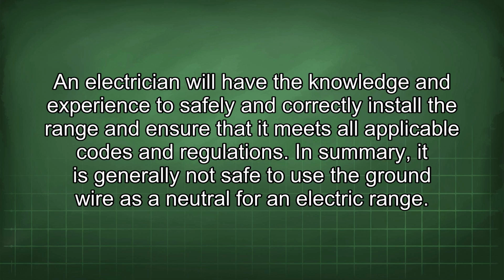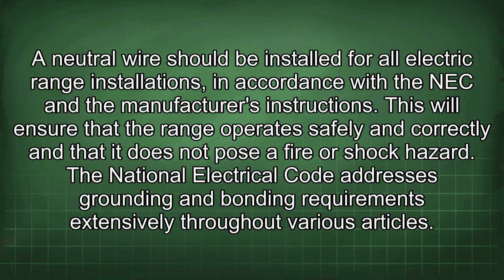In summary, it is generally not safe to use the ground wire as a neutral for an electric range. A neutral wire should be installed for all electric range installations in accordance with the NEC and the manufacturer's instructions. This will ensure that the range operates safely and correctly and that it does not pose a fire or shock hazard.